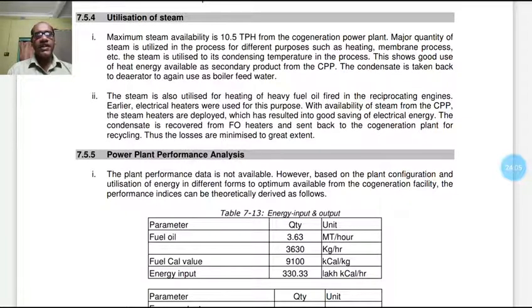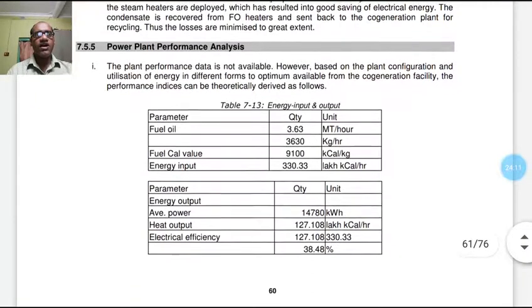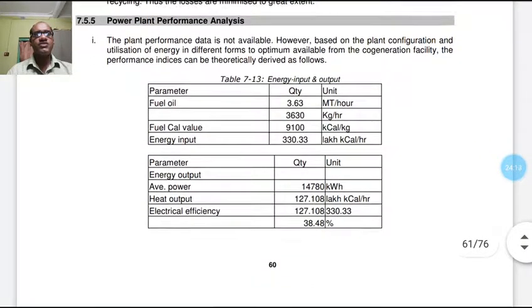Next is power plant analysis. The plant performance data is not available, however, based on plant configuration and utilization of energy in different forms to optimum availability from the cogeneration facility, the performance indicators can be theoretically derived as follows. Fuel oil quantity is 3.63 metric ton per hour. Calorific value is 9100 kilocalorie per kg. Energy input is 330.33 lakh kilocalorie per hour.